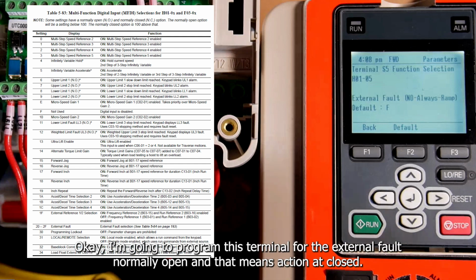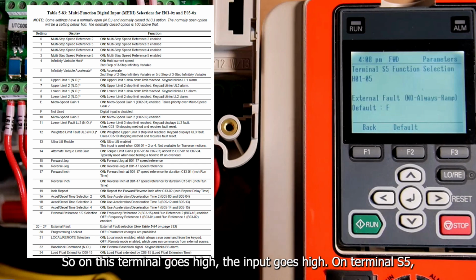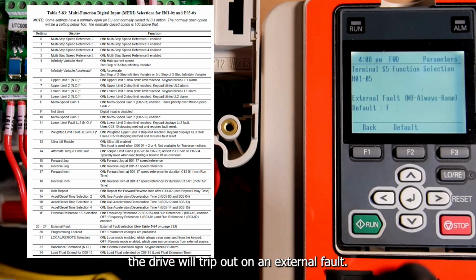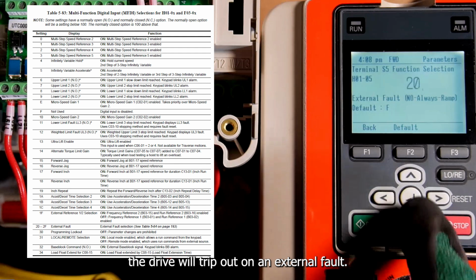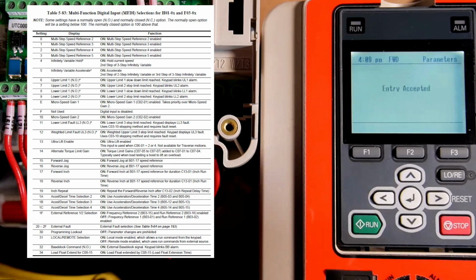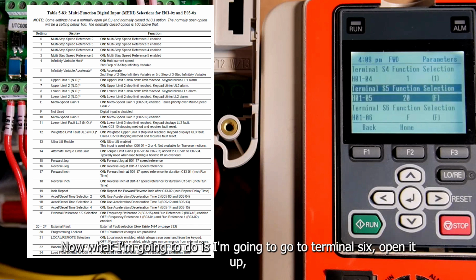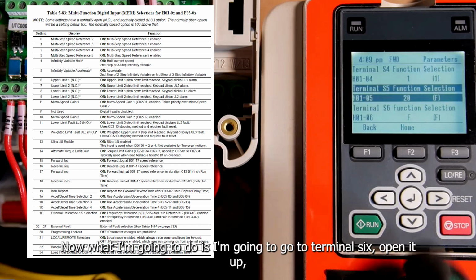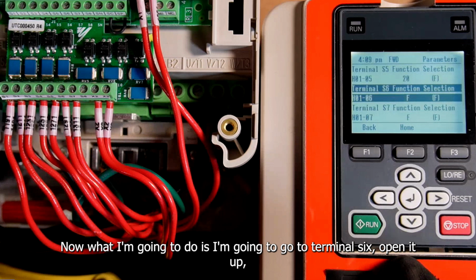Okay, I'm going to program this terminal for the external fault, normally open, and that means action at closed. So when the input goes high on terminal S5, the drive will trip out on an external fault. I'm going to lock it in. Now, I'm going to go to terminal S6.